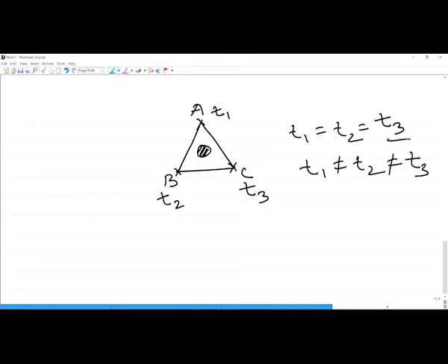Okay. So, this is how when you place a number of sensors around particular locations, this will give you an idea based upon these different times that these sensors receive the signal at, and that is how the zonal location technique will indicate the zone or the location from where the acoustic emission signals are coming out.